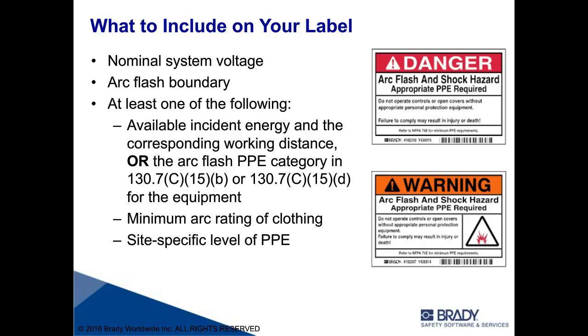The code then goes on to say at least one of the following. It talks about available incident energy and working distance, or arc flash PPE category, minimum arc rating of clothing, or the site-specific level of PPE. What I like to draw attention to here is that first one, the available incident energy and corresponding working distance, or arc flash PPE category. The available incident energy is what we just talked about. That's that 1.2 calories per centimeter squared, 4.8 calories.